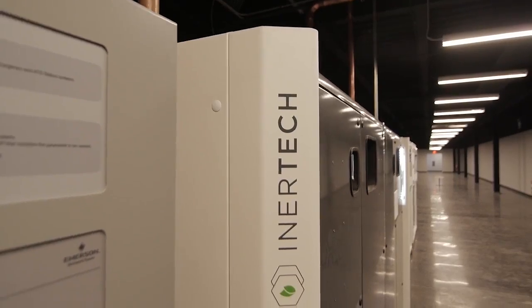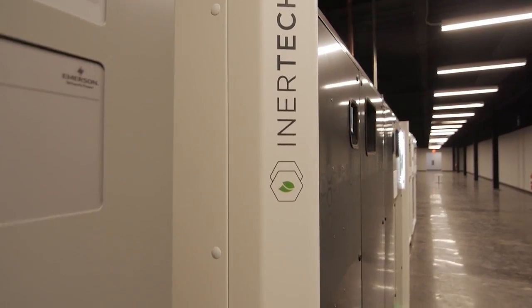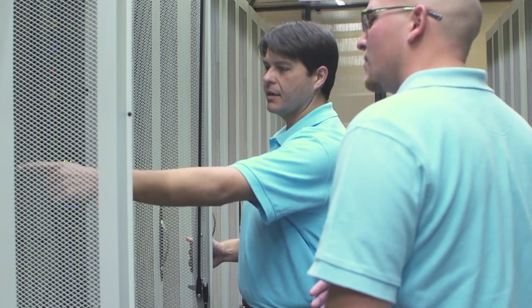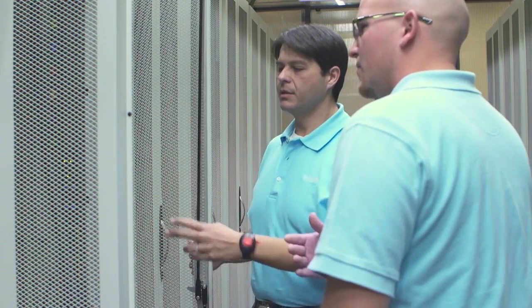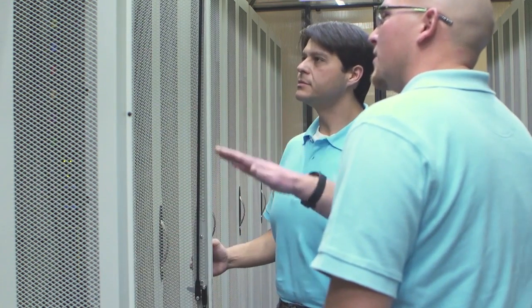And that's the worst case scenario. I've commissioned to 100% capacity. How is my system supposed to operate under this environment in the worst case scenario? And if we're deviating from that, it immediately has us focused on that equipment and what the issues are and how to treat them.